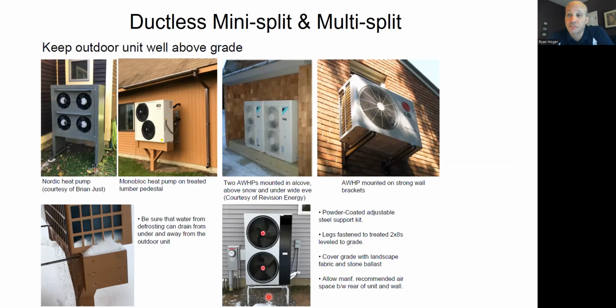Additionally, if you're in an area that has snow, which you are, you're going to want to raise it up above the normal snow line, because if I have snow drifting up on the side of it, it's going to pack on the bottom of the heat exchange surface, and that's going to reduce my heat transfer, and it could eventually also freeze up my coil that way, because now new water running off of it lands on that snow, and that becomes ice, right? And then new snow stacks on top of that. So you have to raise heat pumps up, and you got to raise them up above the snow line. How high? That's always an argument.